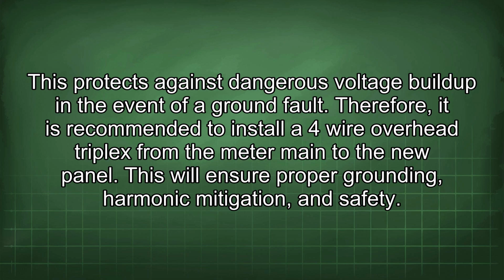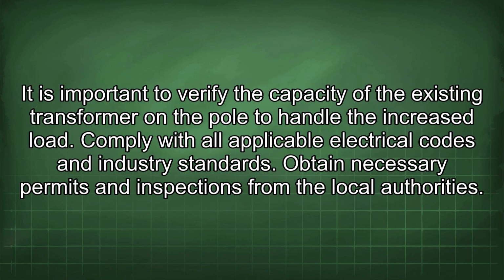Therefore, it is recommended to install a 4-wire overhead triplex from the meter main to the new panel. This will ensure proper grounding, harmonic mitigation, and safety. It is important to verify the capacity of the existing transformer on the pole to handle the increased load. Comply with all applicable electrical codes and industry standards. Obtain necessary permits and inspections from the local authorities.